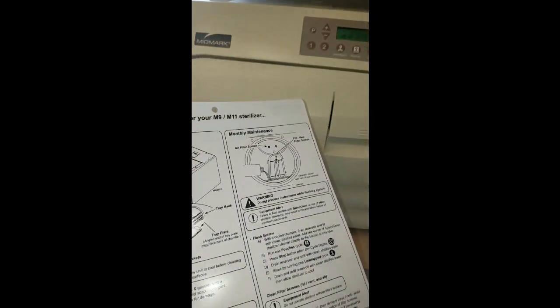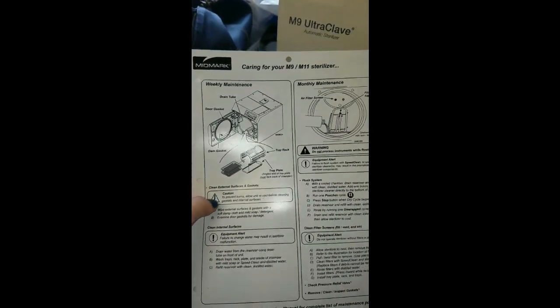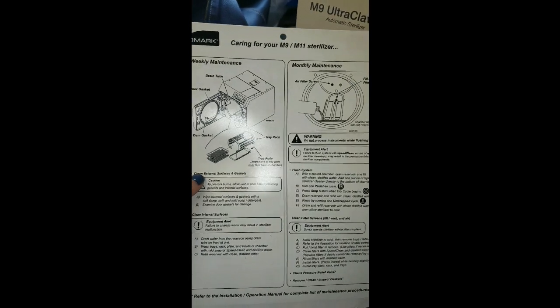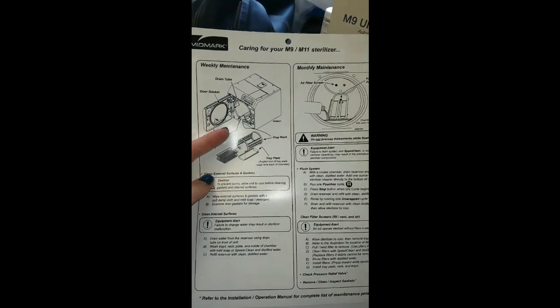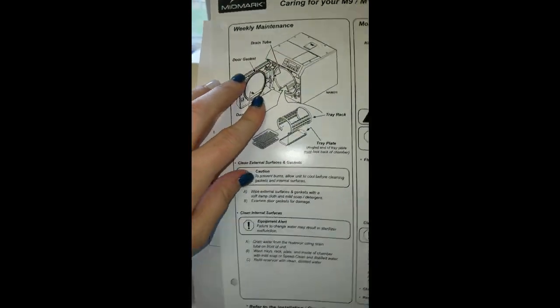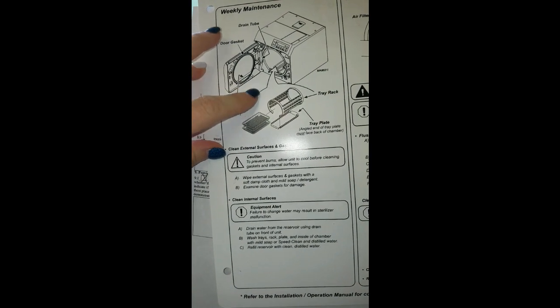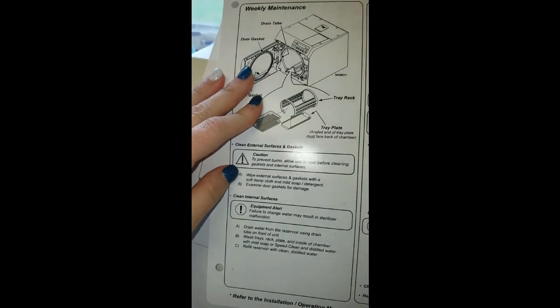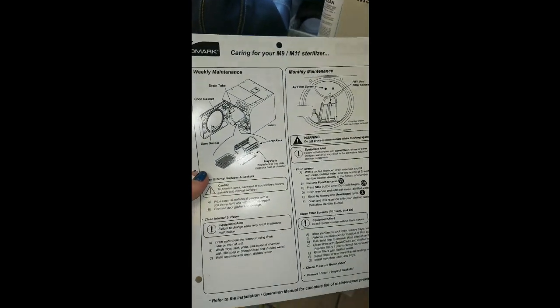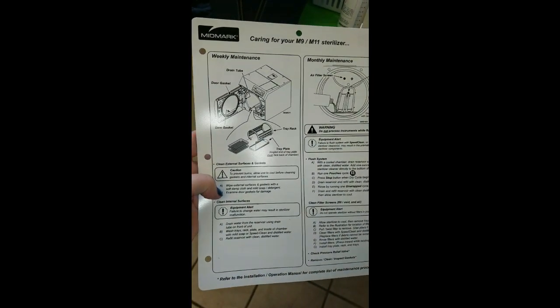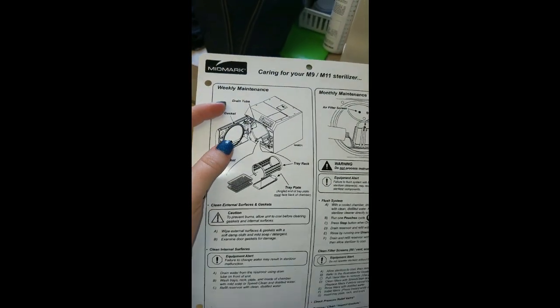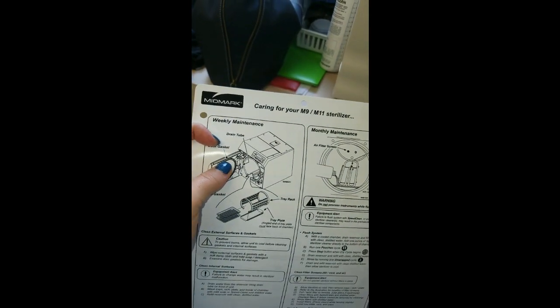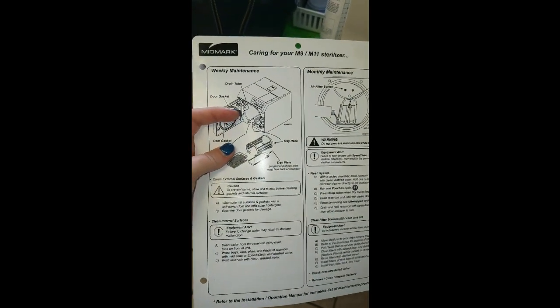So I'm going to describe how we maintain our autoclave. I have the autoclave here. It is actually running right now. All the autoclaves should come with a little cheat sheet here. And what we usually do whenever we do a weekly maintenance is we have our drain tube, and it shows the door and what the inside looks like. Whenever we open it, we just wipe everything down with soap, just a mild soap, nothing fancy. And then we also make sure that the door gasket here doesn't have any broken parts to it, like the rubber's not cracked or anything.